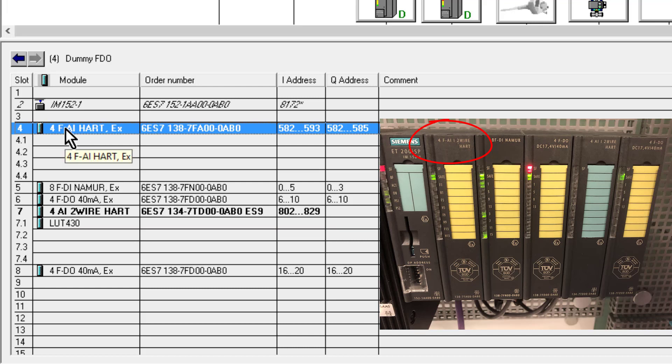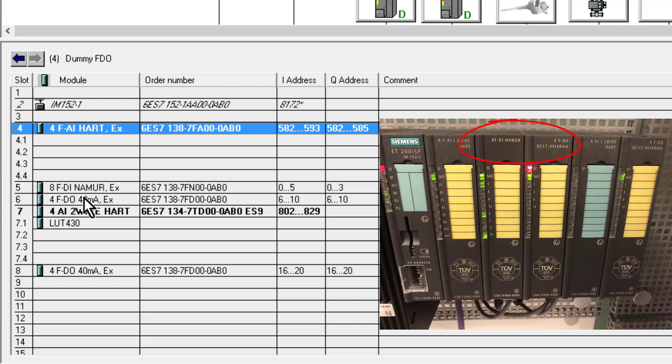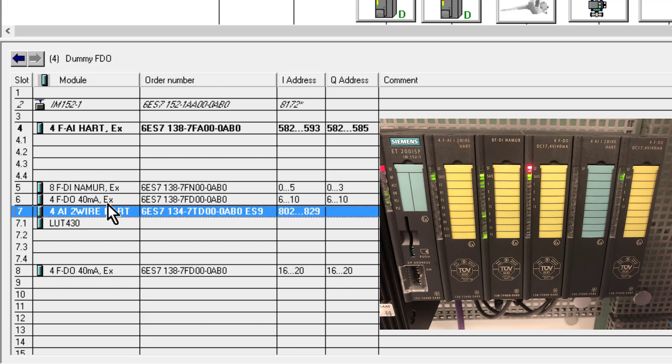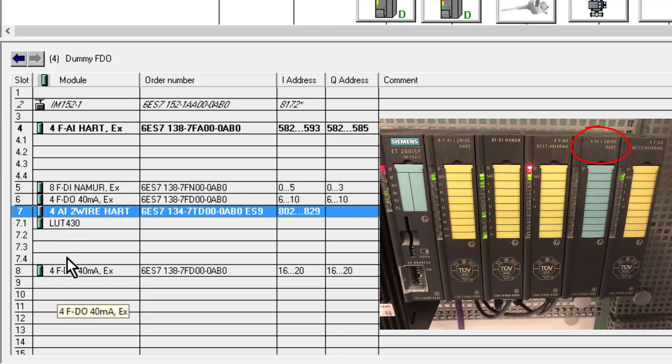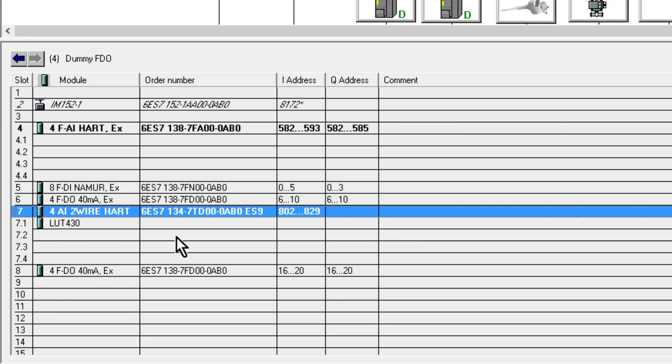The really nice thing about Siemens I/O is you can mix safety I/O with standard I/O on the same rack. Then I have some digital inputs and outputs, and then I come down to a standard two-wire HART input card. You have to be careful here—you have a two-wire option or a four-wire option, and you can't mix and match within the same I/O card.